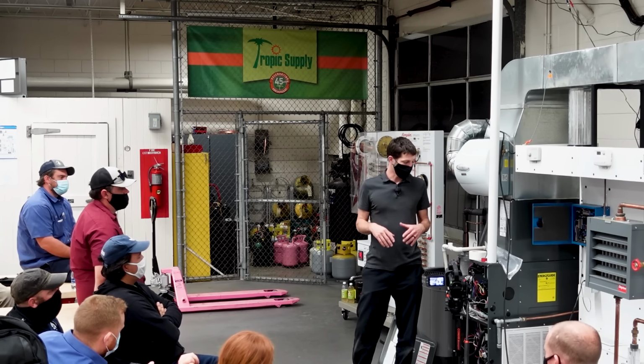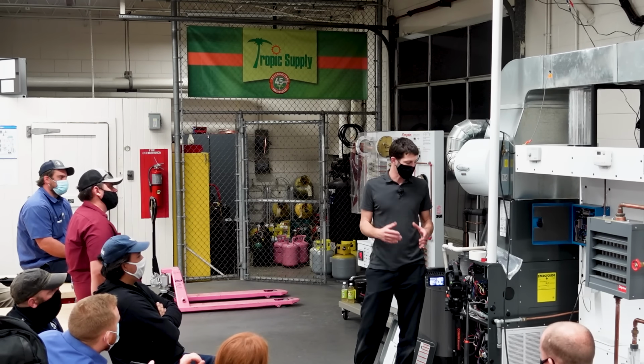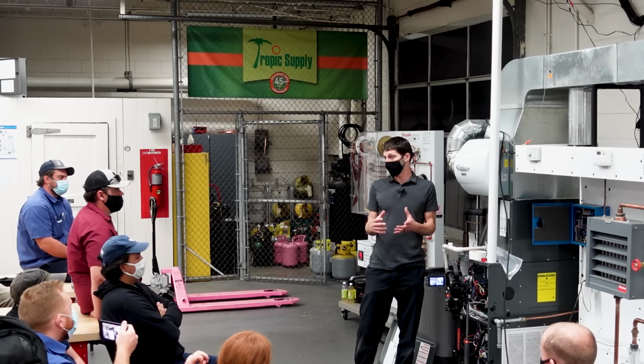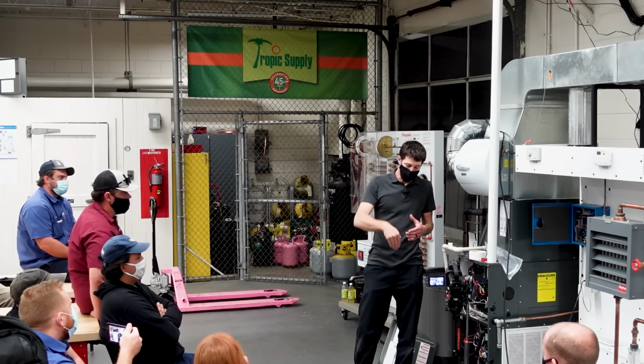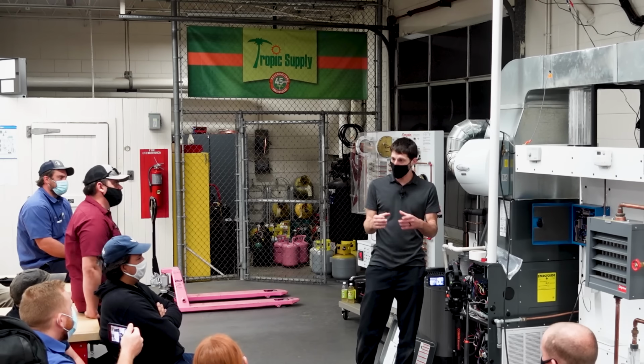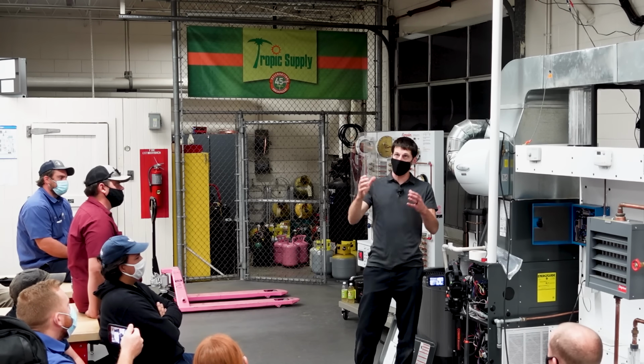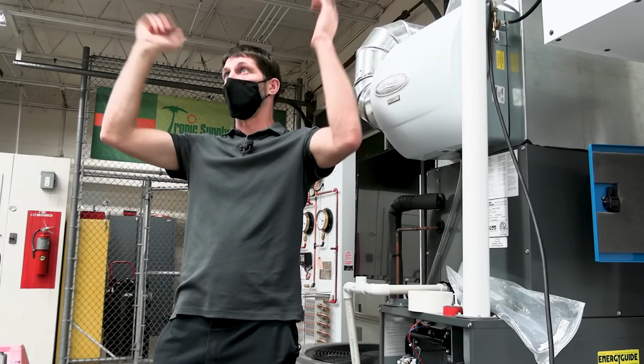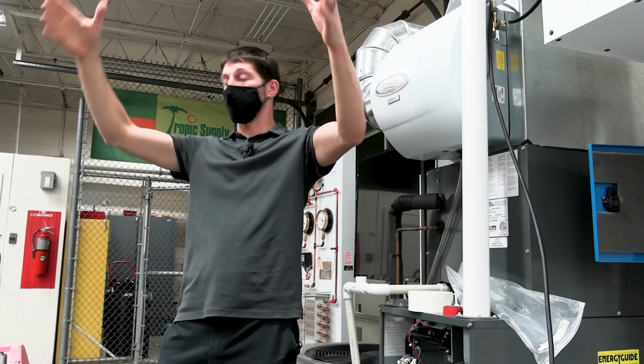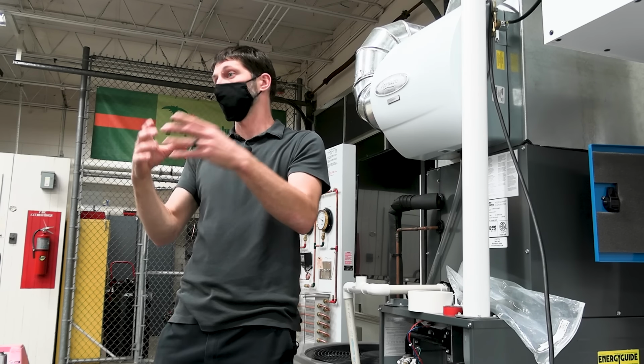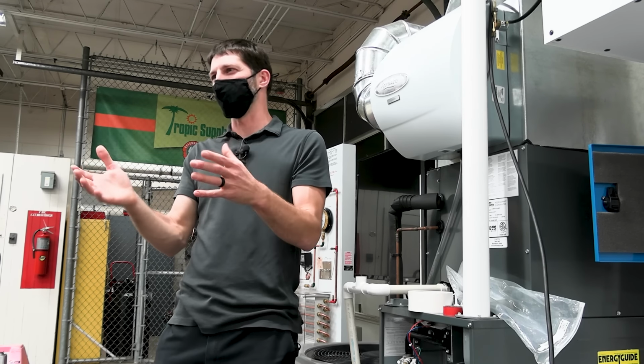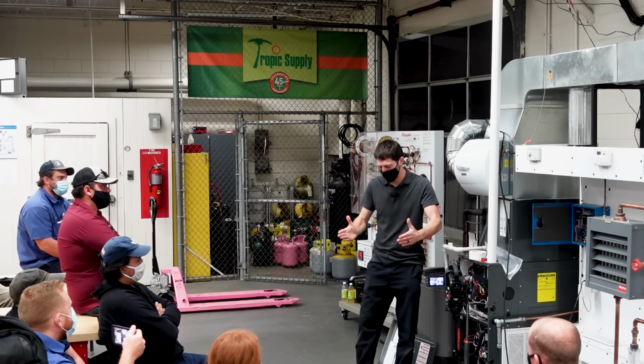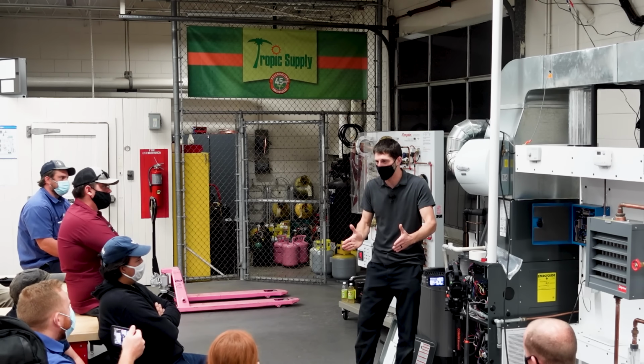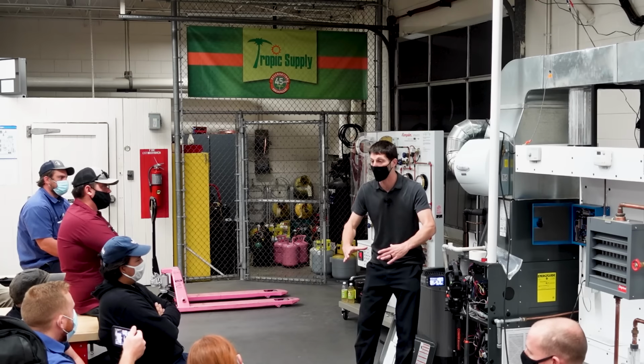So if you were going to orphan the water heater, you are going to need to rerun the exhaust pipe, and you can run new through the old piping and just run 3-inch instead, but you're going to have a new termination. So basically up on the roof, you would have to put a new flange that's smaller, and that's kind of hard too, because you have this large hole, and then you got a new flange. It's only like 1.5 inches on both sides bigger than the actual hole.